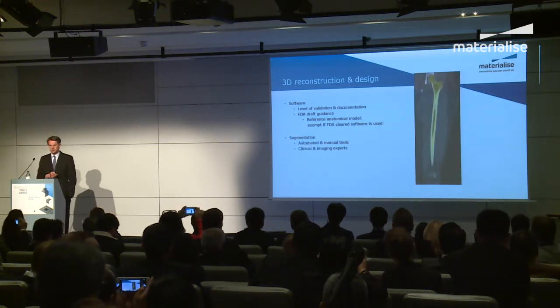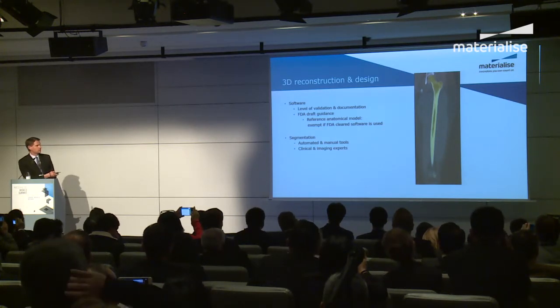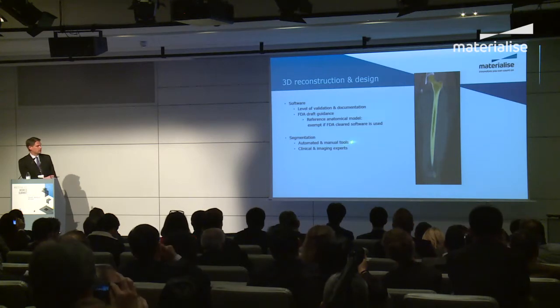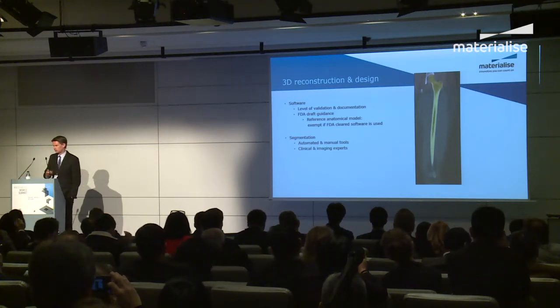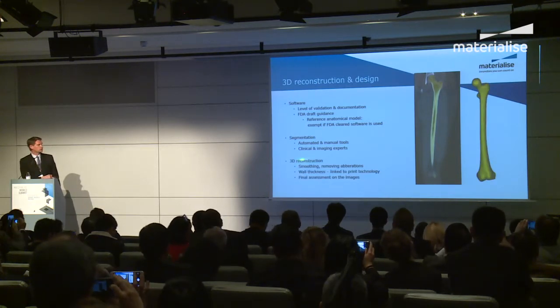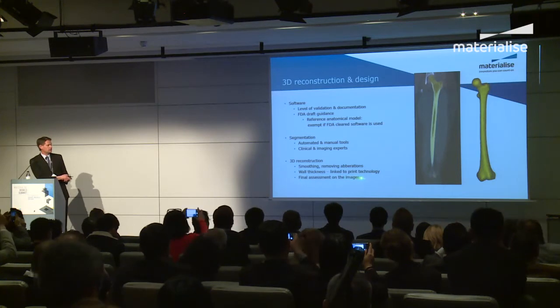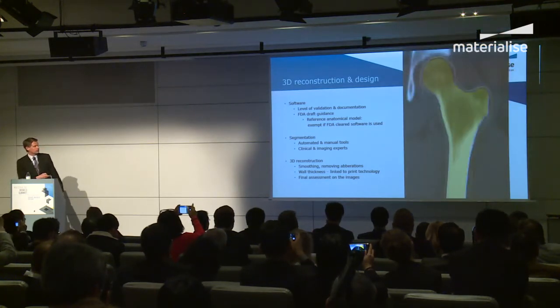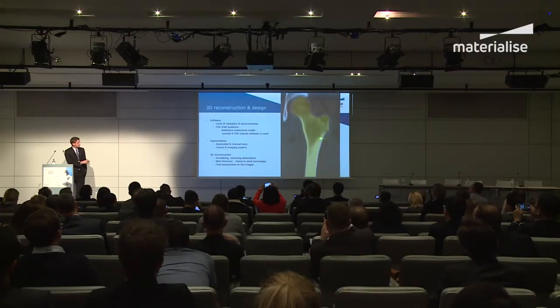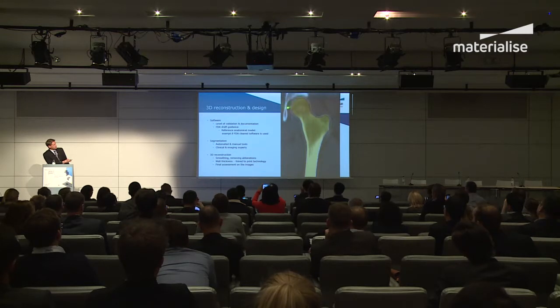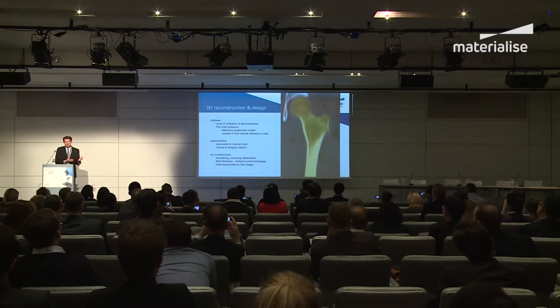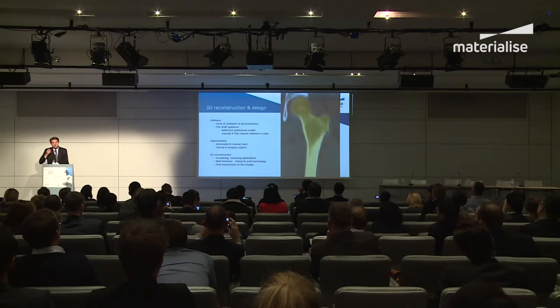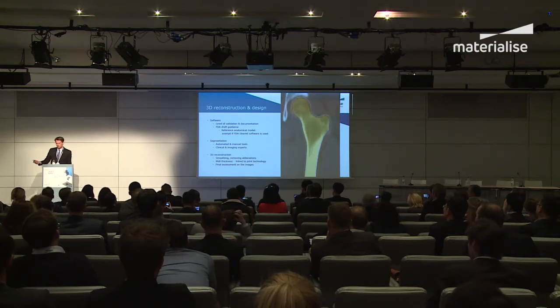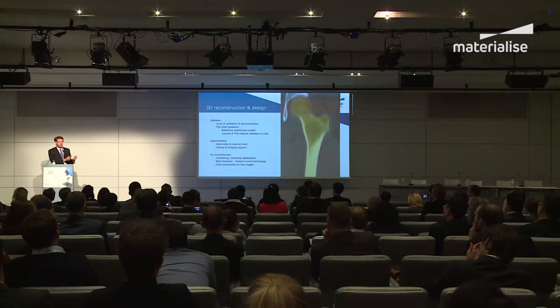Good. You have your software in place. You're going into segmentation. Yeah, you can use plenty of tools to do so. But at the end of the day, you have to demonstrate that you have people, again, that are trained, that are doing this, that are creating the 3D reconstruction. And when doing the 3D reconstruction, you also have to make sure that at the end, that you can do a final assessment on the images. So if you look at this example, I hope you can see that. You can do a segmentation, and then you can either get here the yellow line, or you can get the red line, which is the border of your 3D model, which has been copied back onto your images as a quality check, with very much the same process, with a very small variation in the parameters that you use. You can come to either result. And you have to demonstrate that you know, okay, which is the right one, and is this sufficiently good for the application I'm going to use it for.